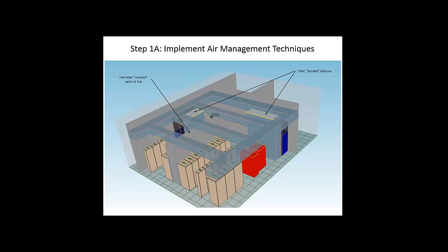So what I tend to do is I turn the RTI up, specifically the incoming flow rate down of the air handlers, until I start to see some RCI high problems, and then I look for opportunity to improve air management. And in this model I did two things. One is I put these snorkels onto the cooling units.